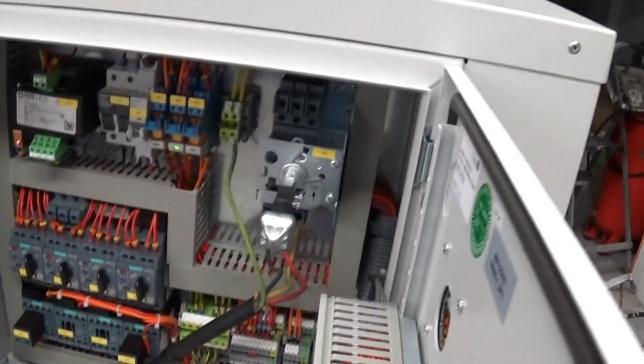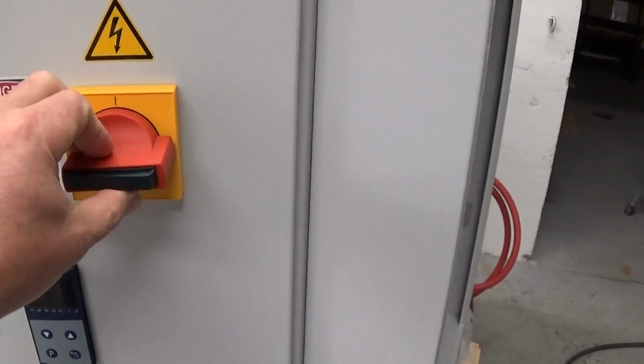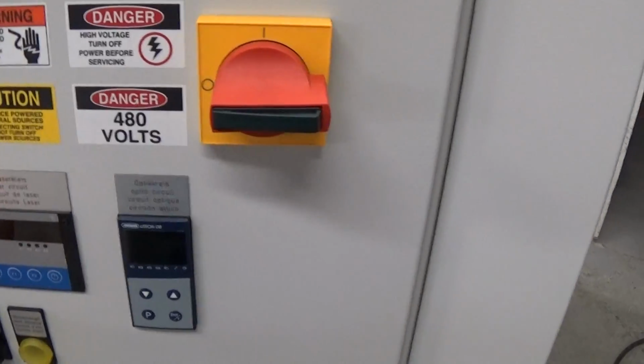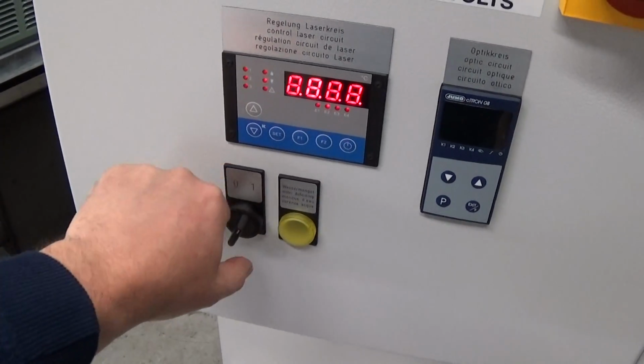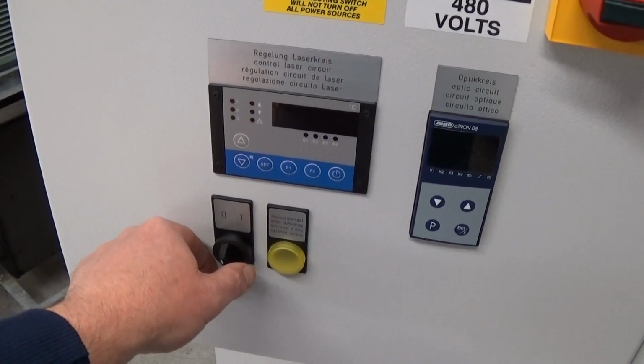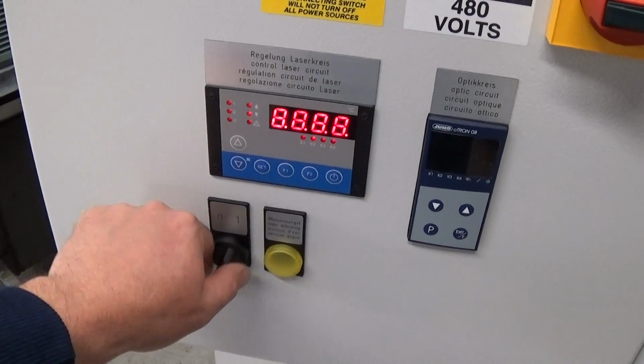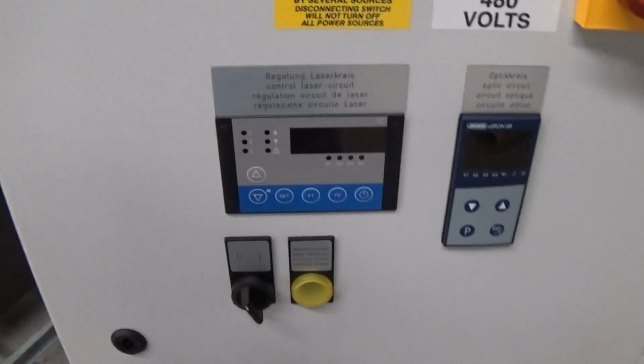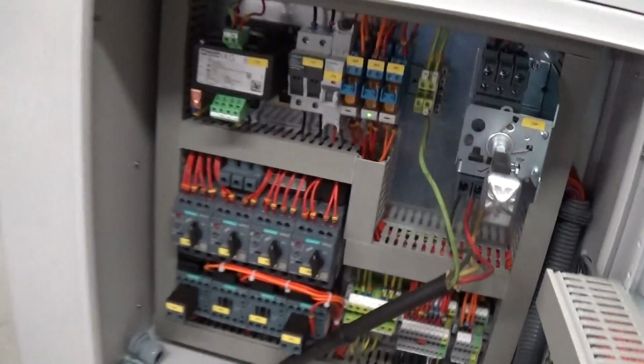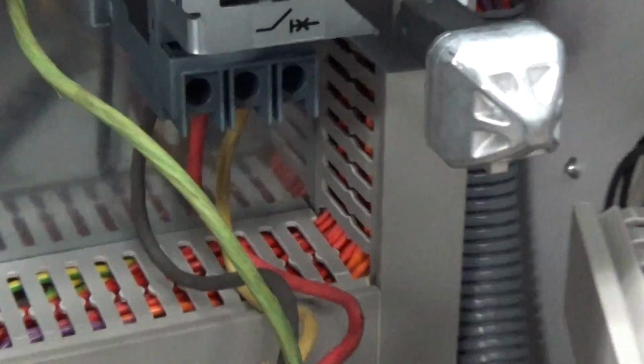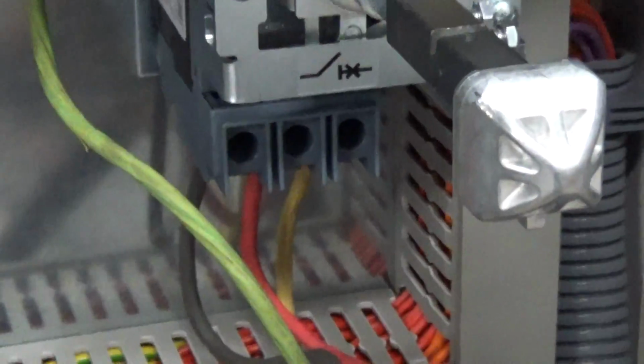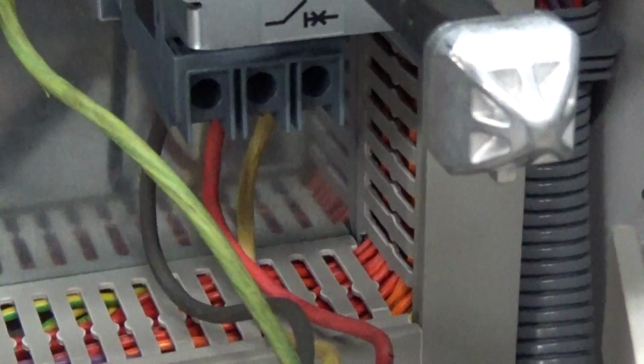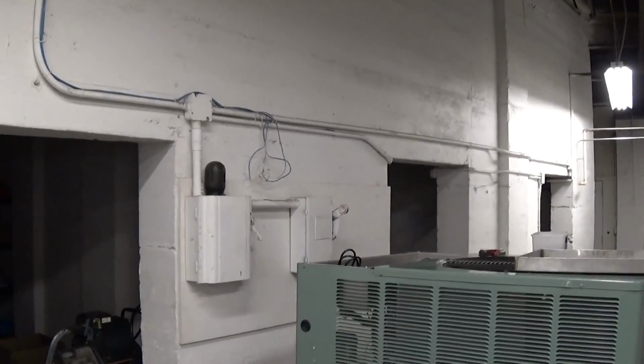Now right now I cheated. I have the disconnect power on here, so typically you want the power off if the cabinet is open. That's all you're going to do to check the phase rotation. Okay? If it's not rotating correctly, do not change anything other than 2 of the 3 main incoming power leads that you see here on your main disconnect. And obviously before doing that, you want to disconnect the power at your main breaker. In our case, it's a disconnect on the wall over there.